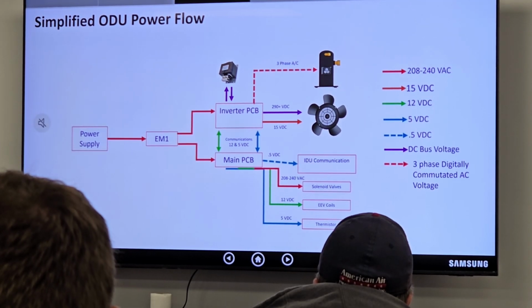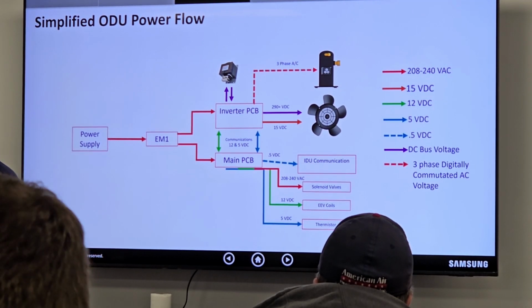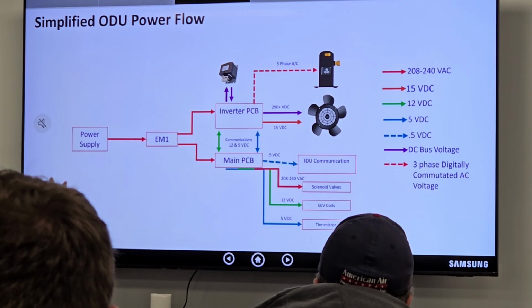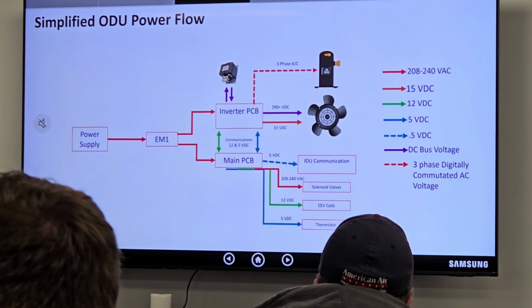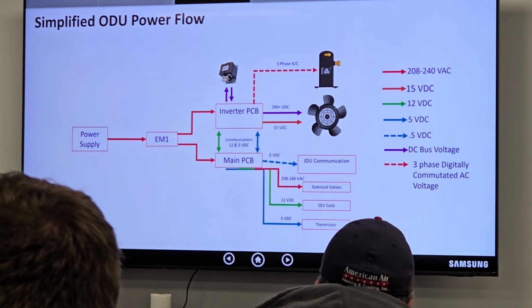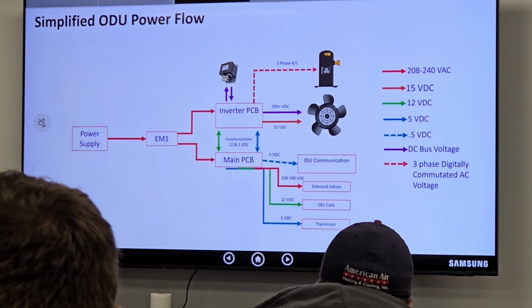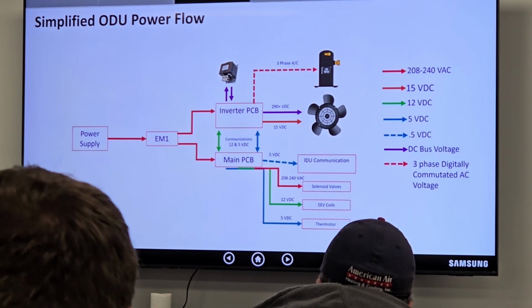Now, can I sit here and tell you I've ever had an issue with the shield? Not that I can tell you, because most of the time on an RAC unit, how far does this run? Up the wall and through the wall, right? But at the same time, we can have interference, so we have to make sure we talk about that as well. This is a 16-2 stranded. Can you use thermostat wire? That's your call. But if you call me up and say you got thermostat wire, guess what I got to tell you? I need you to change that for me.